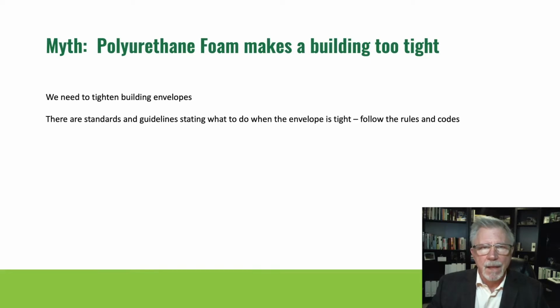That's a good thing. If we make a tight building envelope and we don't address HVAC through use of a HRV or an ERV, heat recovery ventilator, energy recovery ventilator, we miss a critical component of recirculating that indoor air. We must recirculate it. So where we had loose buildings before, 5 air changes, 12 air changes, 15 air changes, we kept up with those air changes by having very large central air conditioning, central heating, HVAC systems. And they were large, they were overscaled.